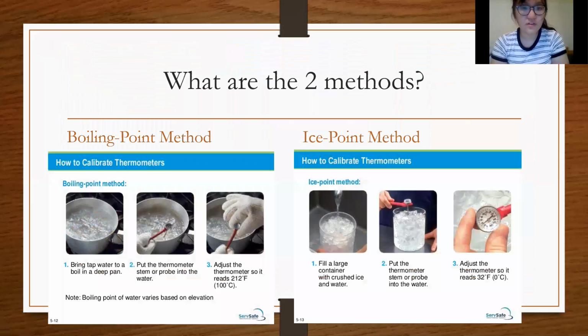And just a quick review, the two methods that we did today are the boiling point method and the ice point method. The boiling point method is to grab tap water and boil it in a deep pan, put your thermometer stem in the water, and adjust the thermometer so it reads 212 degrees. It is important to note that the boiling point of water varies with elevation. For the ice point method, we will fill a container with crushed ice and water. We will put the thermometer probe in the water for about 30 seconds as well, and adjust the thermometer so it reads 32 degrees.